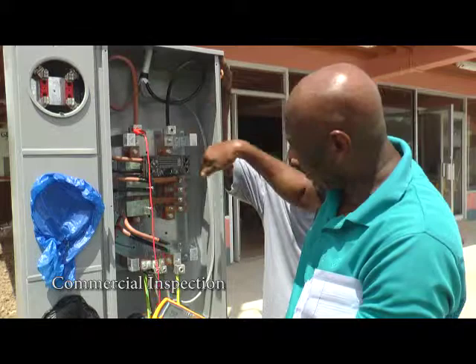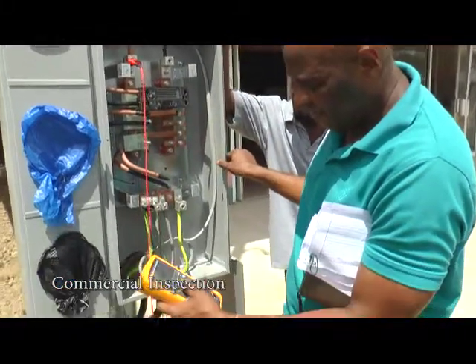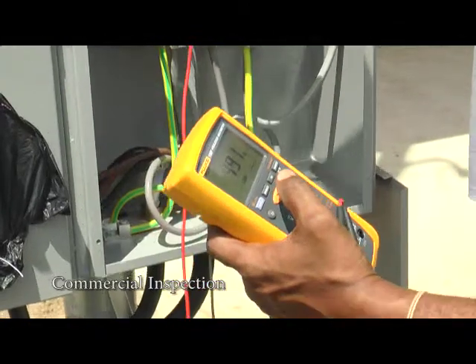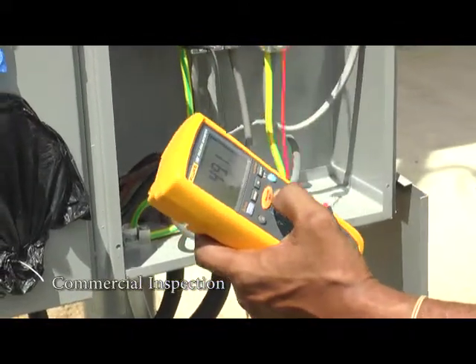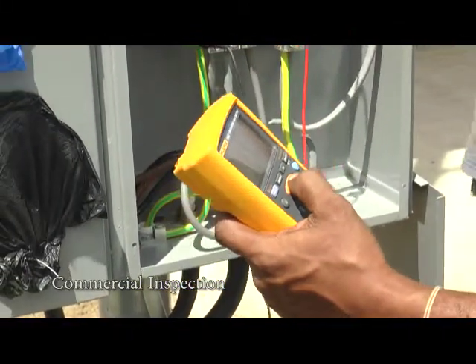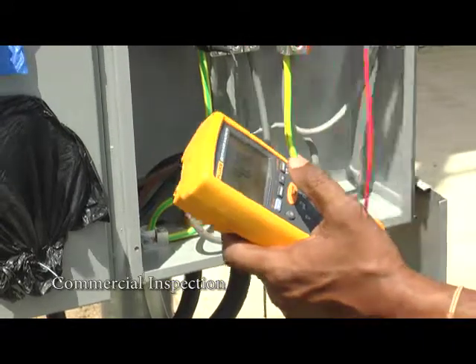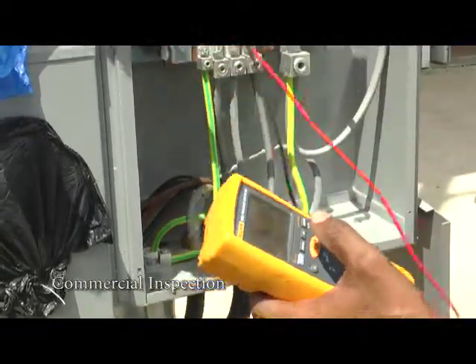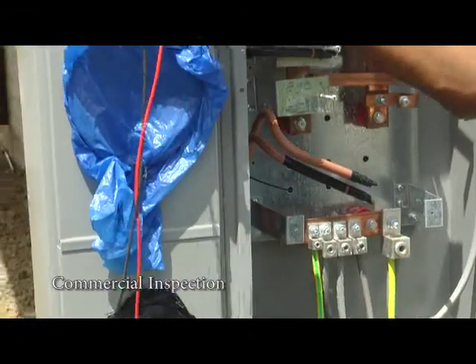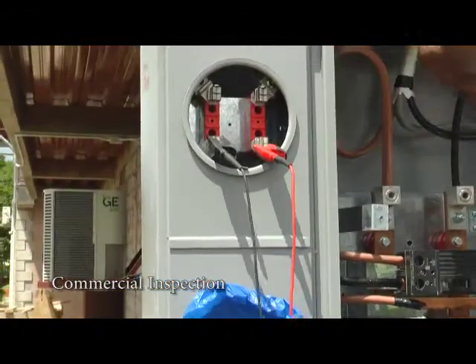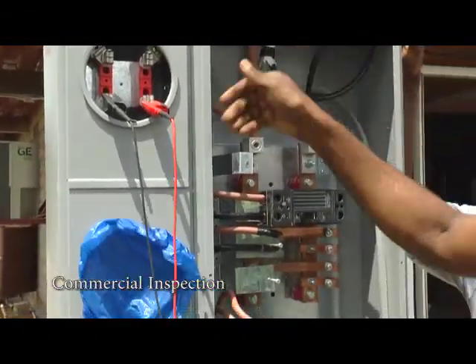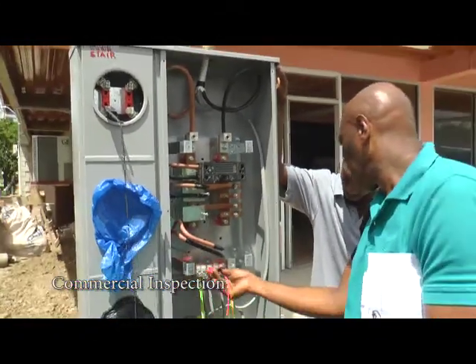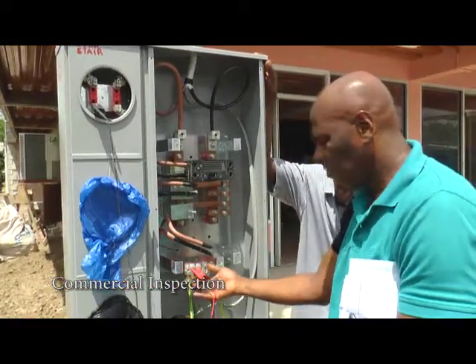So there's a neutral connected. 394, 433, we good. Alright? So I'm going to the other phase. Quite simple. We're good. Alright? Main breaker is off on the inside. So I can ring here. This is the apartment we are testing phase to phase. That's good. Okay.